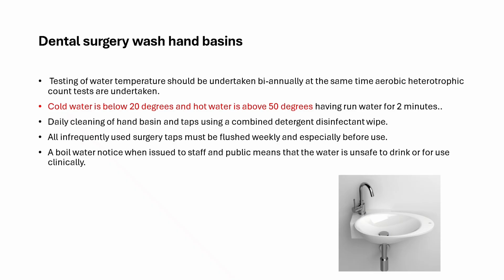Testing of tap water temperature is very important, so cold water should always be below 20 and hot water should always be above 50. In the case of water contamination, a boil water notice may be issued, and in this case, this water can't be used in the dental unit or for hand washing. Always make sure to flush tap water from an infrequently used tap before use, and always, of course, disinfect the sink and the tap.